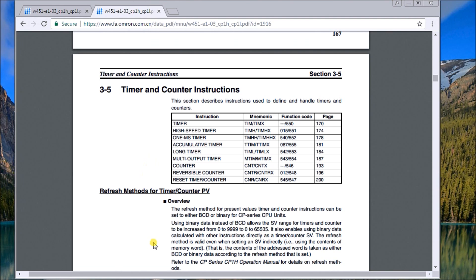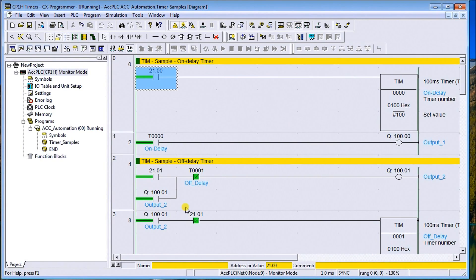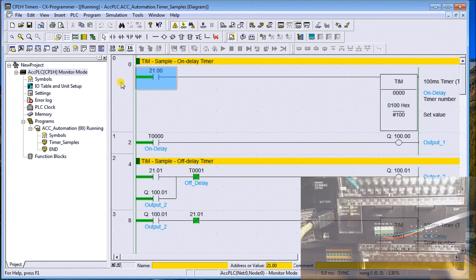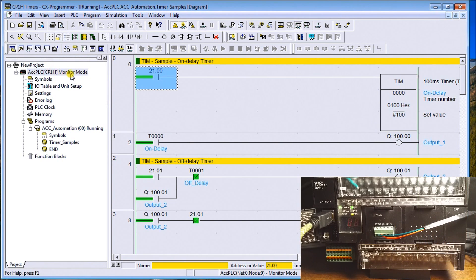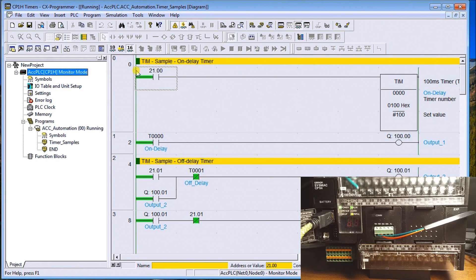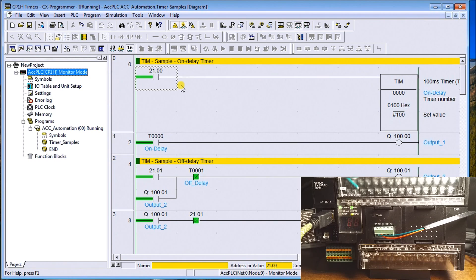Let's dive right in. I'll call up our program — currently I'm online and communicating to the controller. I have an on-delay timer on screen. The on-delay timer can be used with the regular timer, the high-speed timer, and the millisecond timer. The only difference between the three is the timing base rate: the regular timer uses 0.1 seconds, the high-speed timer uses 0.01 seconds, and the millisecond timer uses a 0.001-second time base.